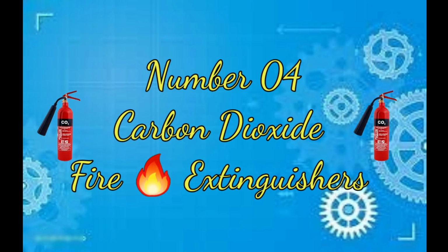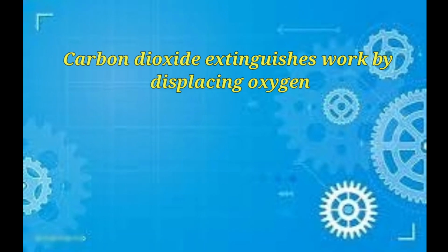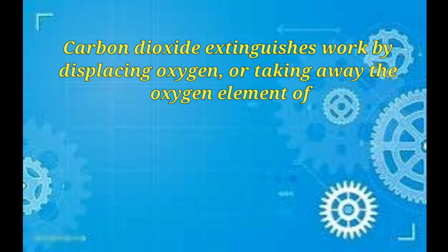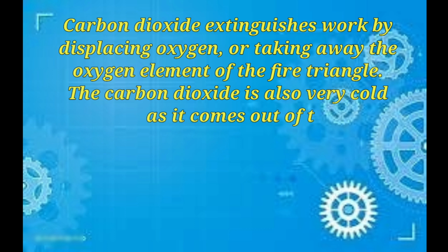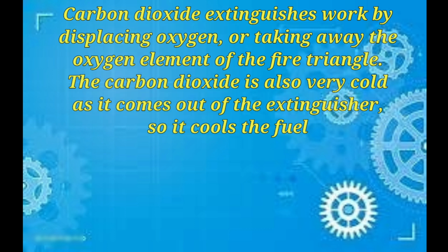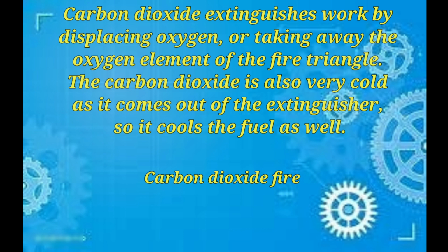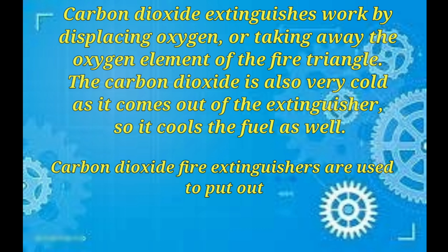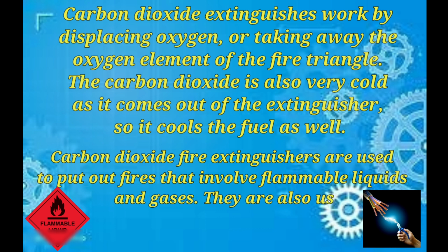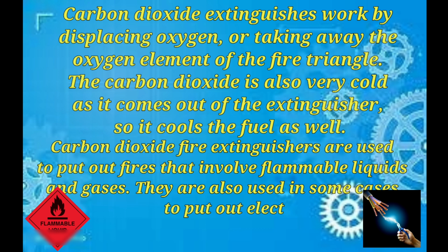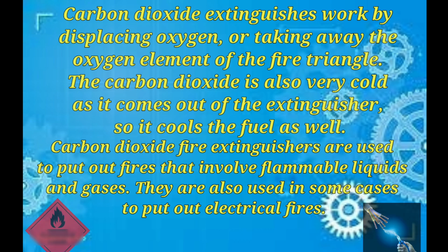So let's go to the other type. Number 4, carbon dioxide fire extinguisher. Carbon dioxide fire extinguisher works by displacing oxygen, or taking away the oxygen element of the fire triangle. The carbon dioxide is also very cold as it comes out of the fire extinguisher, so it cools the fuel as well. Carbon dioxide fire extinguishers are used to put out fires involving flammable liquids and gases. They are also used in some cases to put out electrical fires.